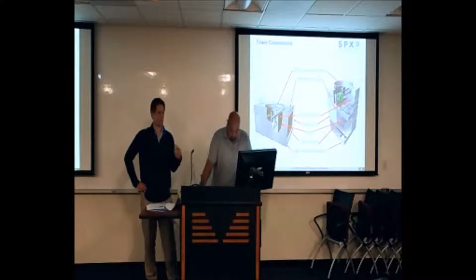Yeah, we're actually the only manufacturer that builds their own gear reducer. So the good news is that it's made for the cooling tower industry. It's made for these conditions. But as Larry mentioned, these aren't something that you'll be able to call the depot and get within a few days. This will be a little bit longer lead time. So a spare might be something to consider with a 3-cell installation. Yep. And are yours the same on each side? Yes, they should be, they are the same. The towers were identical. Typical.